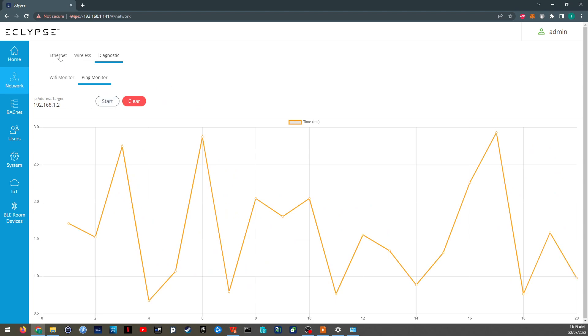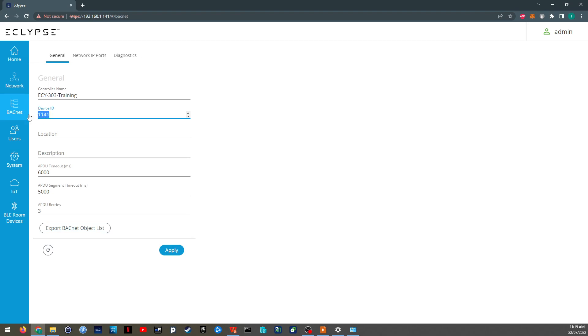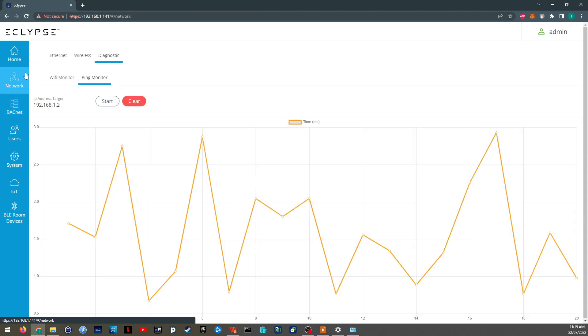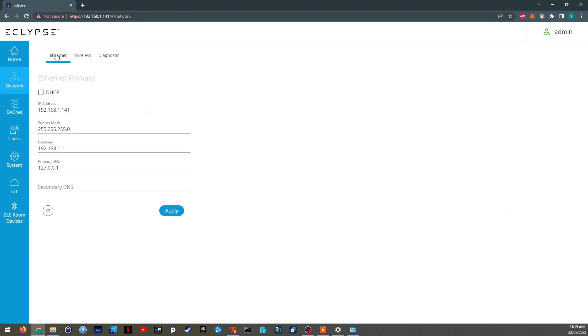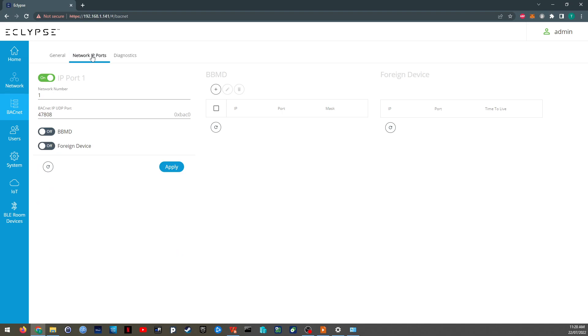Okay, the next tab is the BACnet settings. So the key settings for BACnet IP is the device ID. Once you have the device ID, you don't really need anything else. Sometimes it takes a combination of IP address and device ID. This one has its BACnet ID preset by the network. So the moment that you set this, it'll use a combination of these two numbers here to set the device ID.